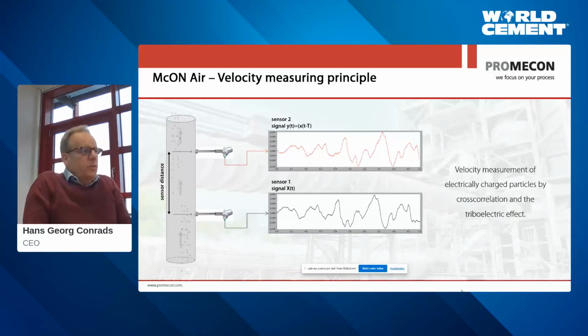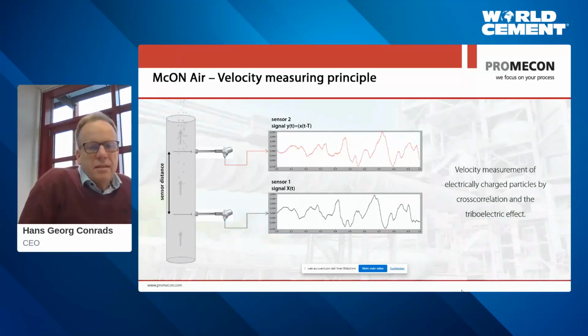Our system consists of two sensors, and these two sensors are basically nothing else than an antenna. The dusty gases that flow through your ducting are usually electrostatically charged. So they all carry a charge that moves by our sensor. And if you look at one sensor, let's say the lower one, you can see a succession of clouds of dust passing by the sensor. And these clouds have a change in density. So the charge that is passing by the sensor is also changing over time. And this change over time induces a current, which we call time signature. The current over time. If you look at sensor 1, you can see the current that would be induced on the sensor over a typical second of measurement.